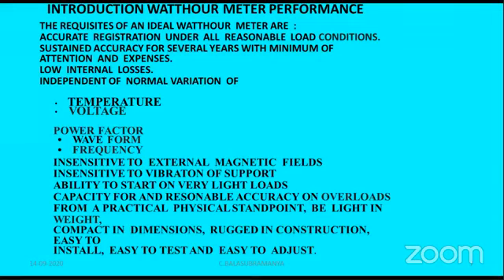What is overload? Overload, in the sense, the meter is designated as, for example, 10-100 amps. 10-100 amps is the designation of the meter on the nameplate. What does 10 imply? 10 implies it is the basic current, the current which is used as the basis for the standard. 100 is the maximum continuous current the meter can carry without distorting the total load characteristics. You just bear that in mind. That means these meters are said to be 1000% overloadable meters, because 10 to 100 is 10 times. These meters are known as 1000% overloadable meters.